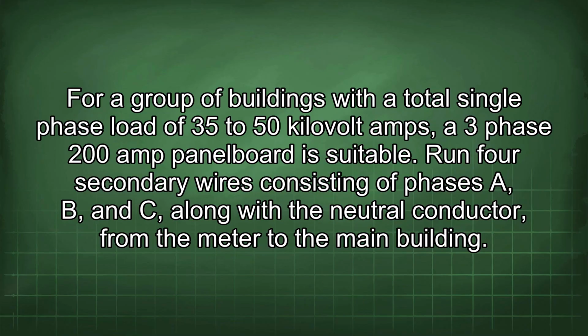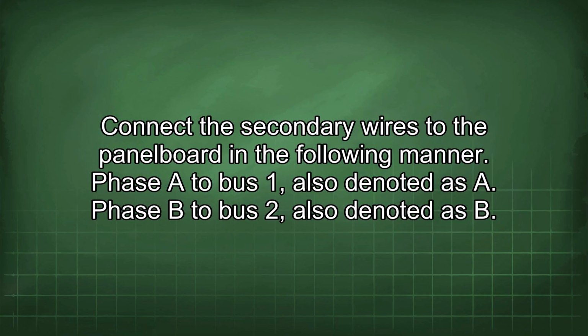For a group of buildings with a total single-phase load of 35 to 50 kVA, a 3-phase 200 amp panel board is suitable. Run 4 secondary wires consisting of phases A, B, and C along with the neutral conductor from the meter to the main building. Connect the secondary wires to the panel board in the following manner.